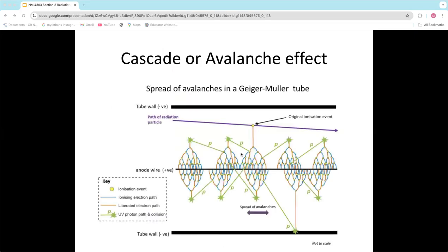Okay, so we need to talk about what's called a cascade or an avalanche effect. This is what happens in a Geiger-Muller tube when we get the voltage up to the Geiger-Muller range. So we're going to follow this through. This purple line up here represents the path of radiation coming in. This radiation, whatever it is, comes in and strikes one of the argon gas molecules. This is the same reaction as in the saturation of the ionization range, where you get that ionization, the ion pair and the electron.